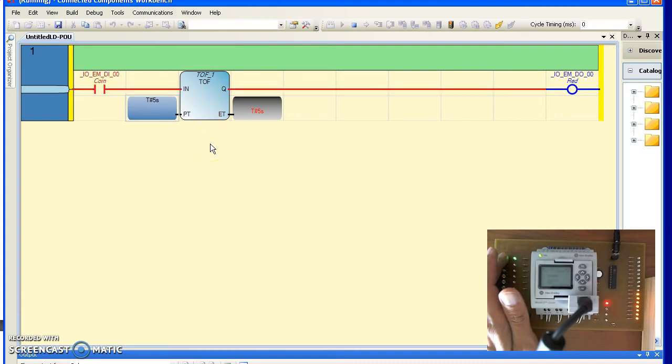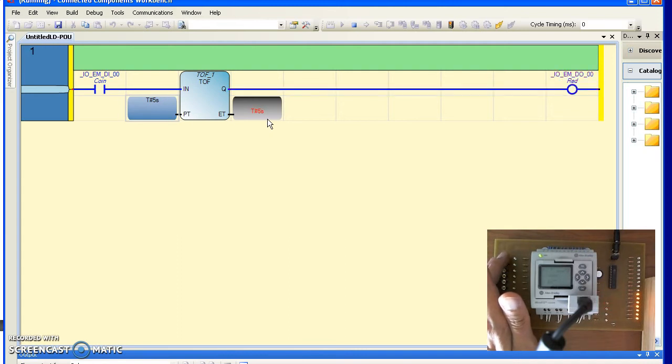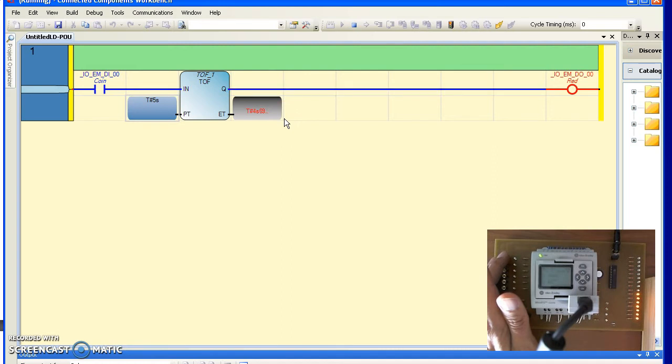When I press the button, the output goes high immediately, stays high. As soon as I release, it stays on for 5 seconds. If I have a momentarily input, the output stays on. 5 seconds after I release, it turns off. That's the T off function.